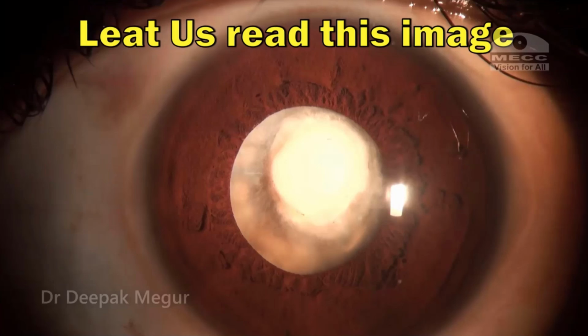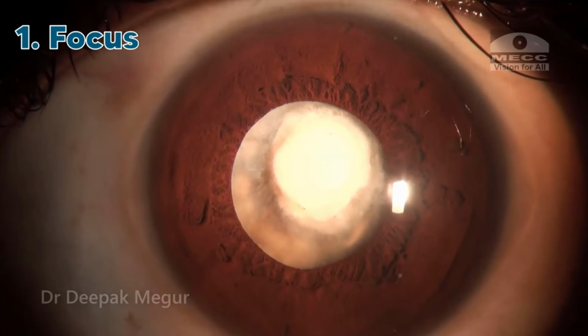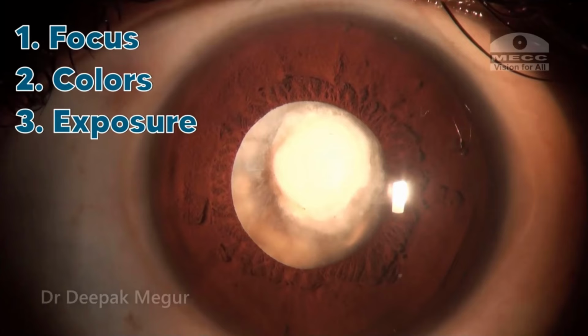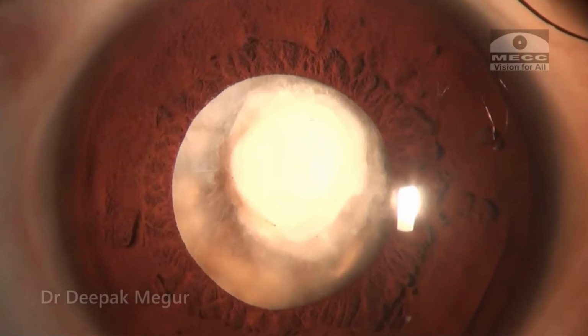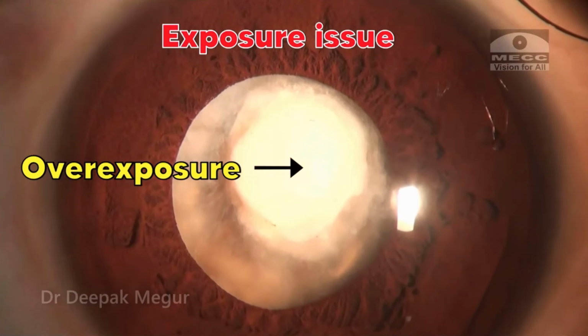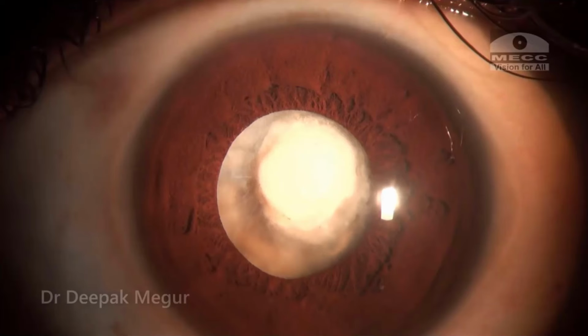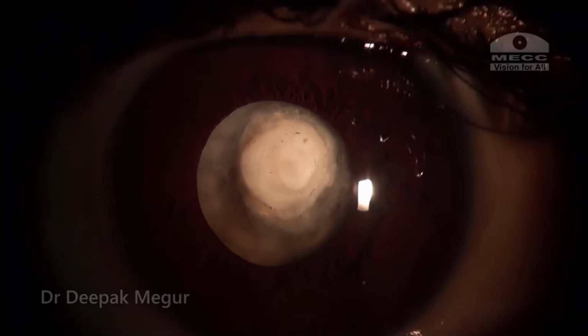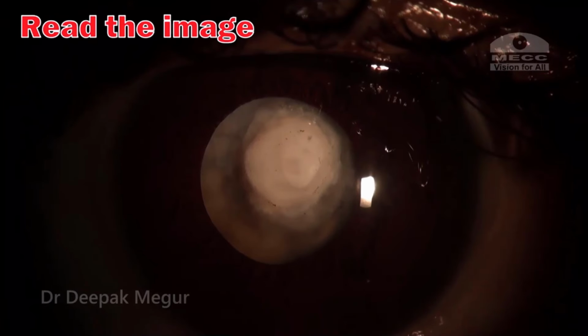Let me just play here. The calcified capsule part is just blown out. The focus is good, colors are good, exposure is good, sharpness is good. But if you want to show the calcification part, that is gone. So you have to reduce the illumination. When you reduce the illumination, the calcific spot comes into focus.